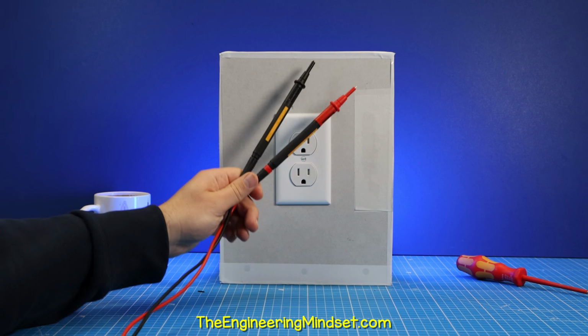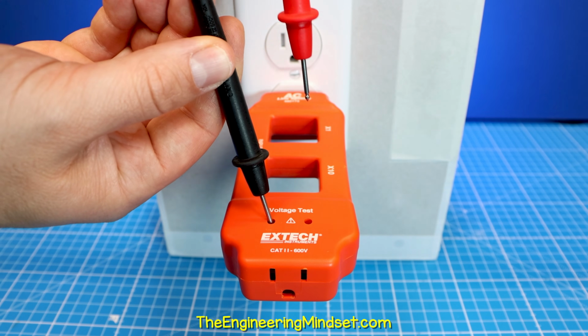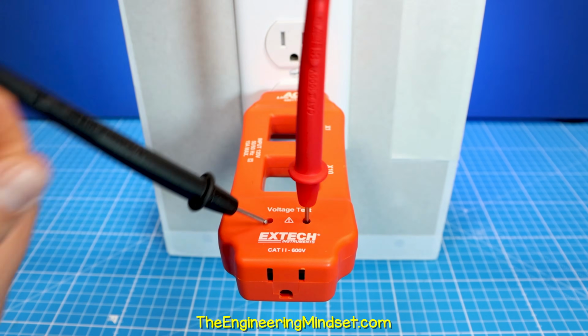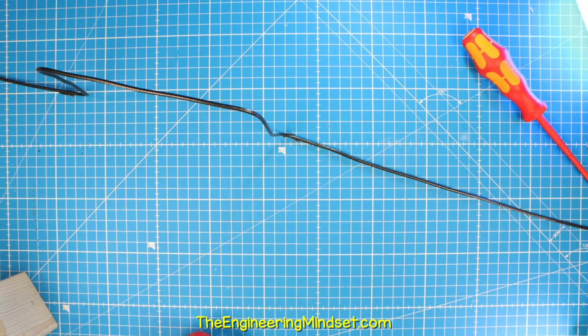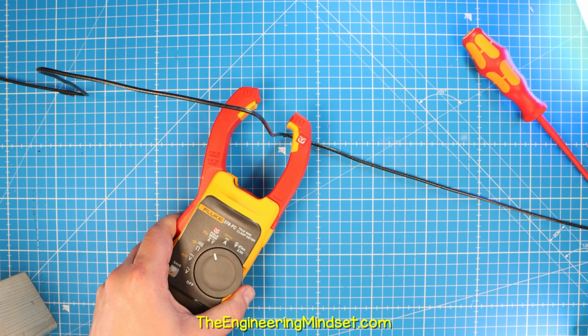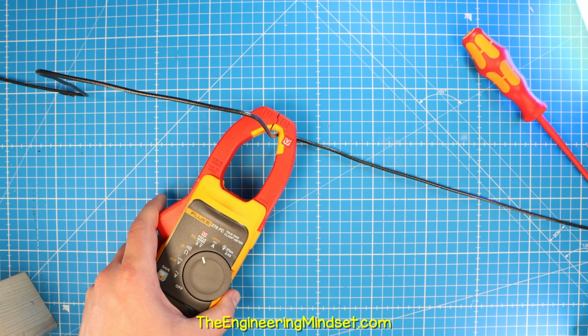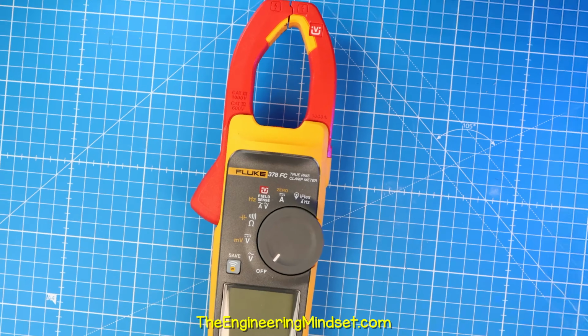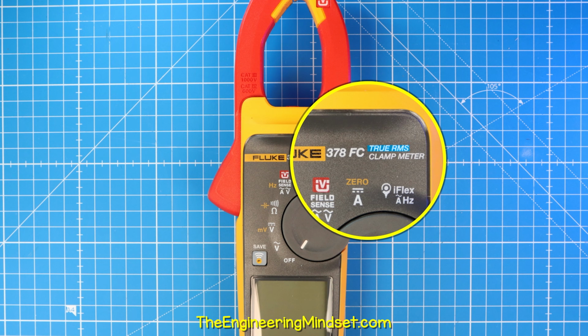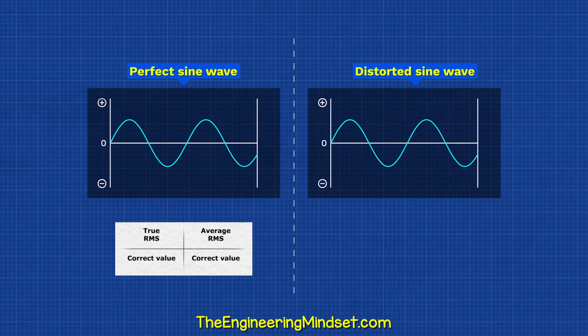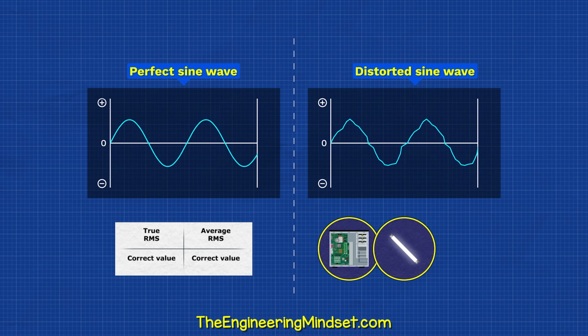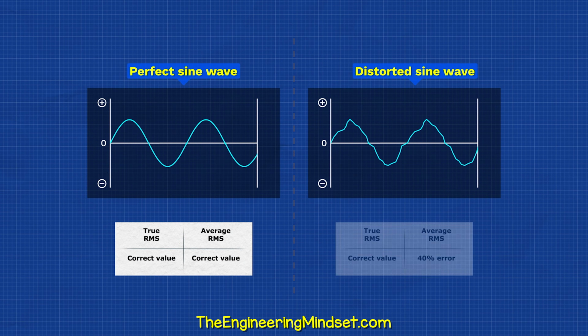To measure AC voltage, we need to use the probes and make contact with the circuit, which can be dangerous. Some clamp meters allow us to use the clamp instead, which is much safer. For best results, make sure yours is a true RMS meter, not an average RMS meter. And that's because PCs, lighting, and speed controllers can distort the sine wave. Average RMS meters will give you a false reading.